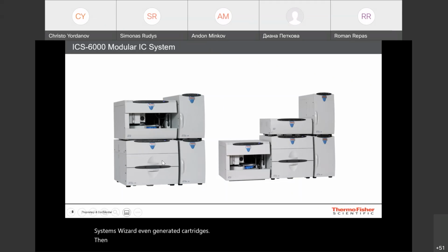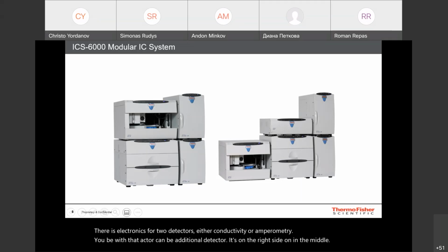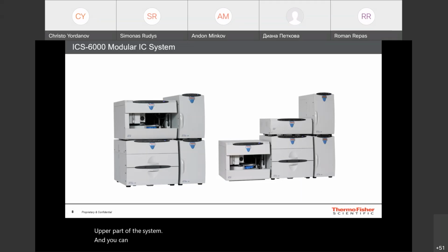Then the system on the left bottom side, which is called DC, which stands for detector and chromatography compartment, integrates injection valves, columns, detectors. There is electronics for two detectors, either conductivity or amperometry. A UV-vis detector can be an additional detector. It's on the right side, in the middle upper part of the system. And you can use one of our three autosamplers. In this case, it's the AS-AP, the advanced performance autosampler for the most demanding applications.